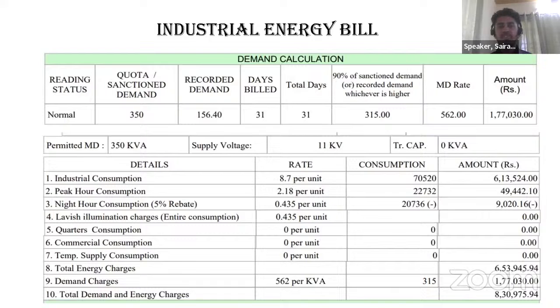Let me take an example of an industrial energy bill to explain how the demand calculation is done. If you see here, the quota or sanctioned demand is 350 kVA. That is an agreement between the user and the grid. They have agreed to purchase 350 kVA sanctioned demand, like contract demand, from the grid during the particular period of 1 month.